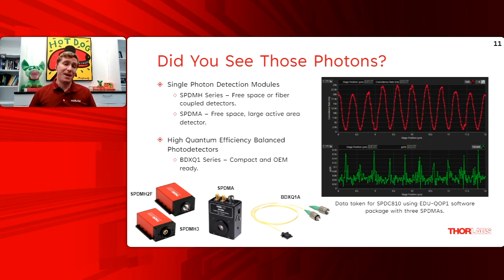The SPDMA, I like in particular because it's got a nice safety system built in that's great for, I guess, newer people to the industry where they might not be as careful with not shining too bright of a source onto it and potentially causing damage. So in that sense, for the kit, it's designed so you can actually use the alignment laser on it without causing any damage. Even if the detector itself is on, it'll just kind of shut off that signal and keep itself from getting damaged.